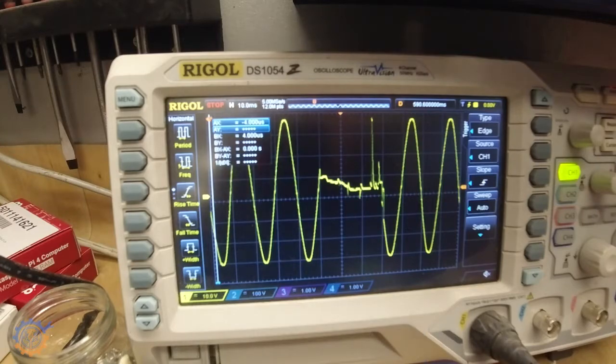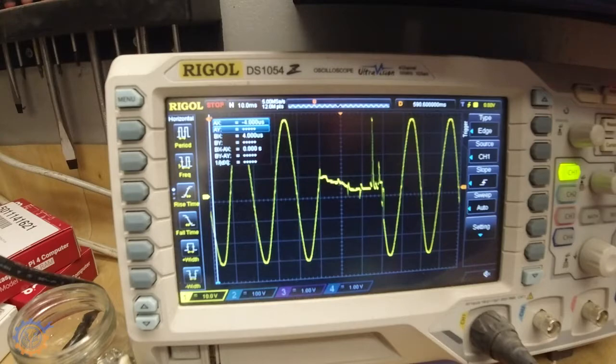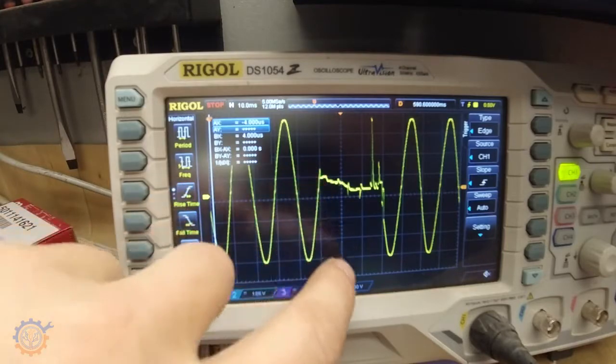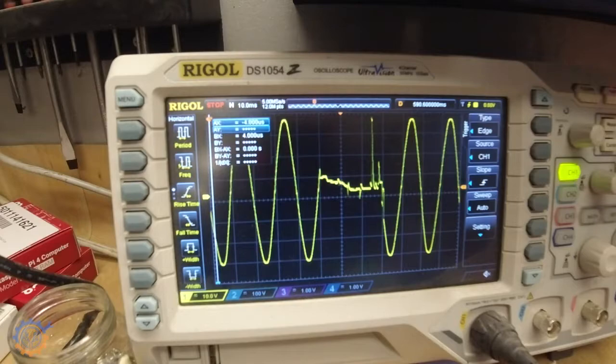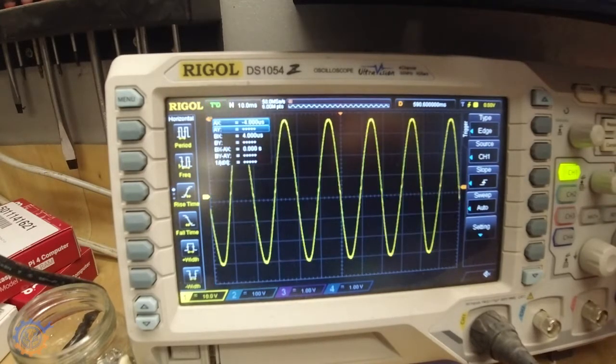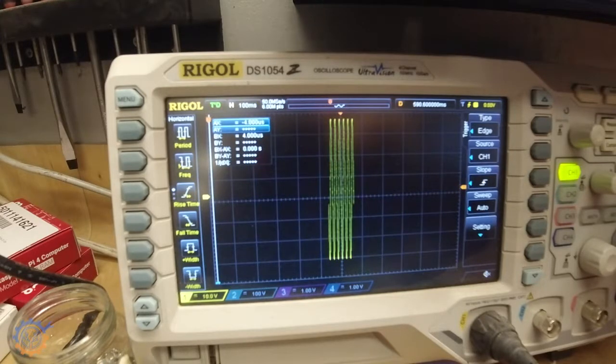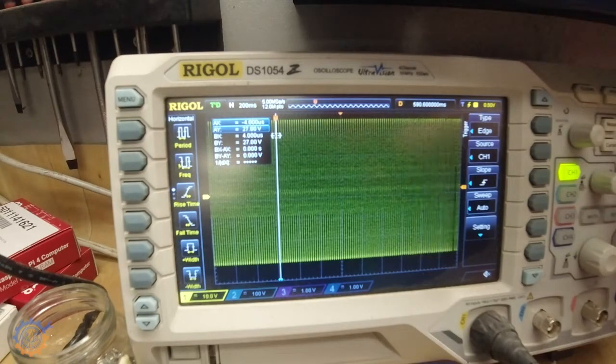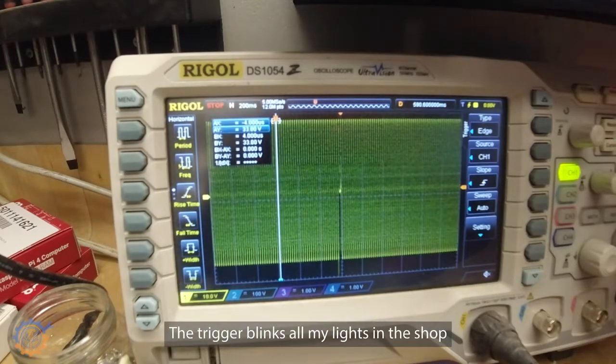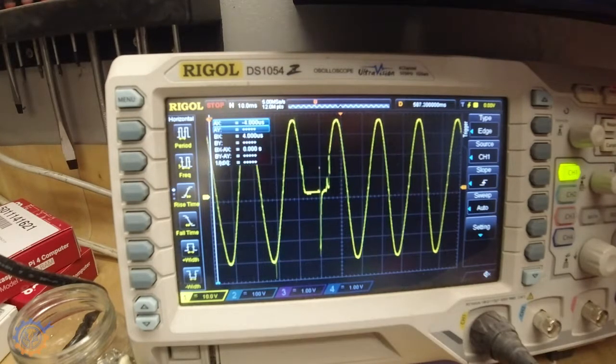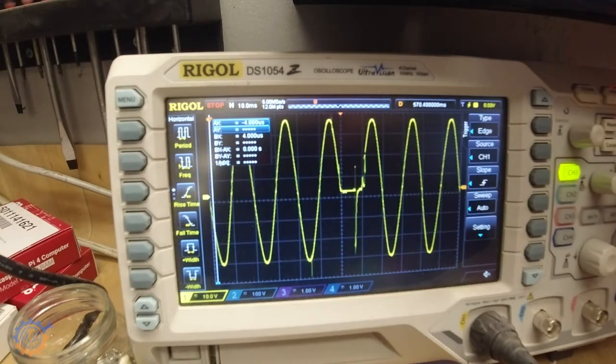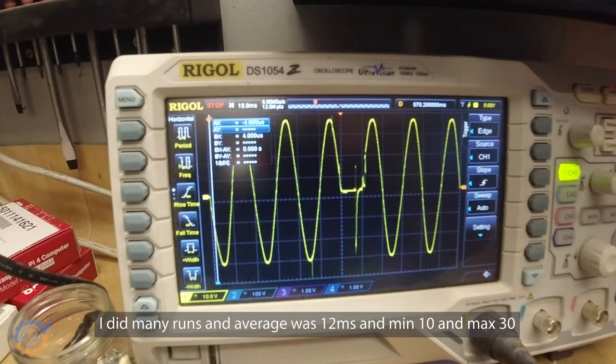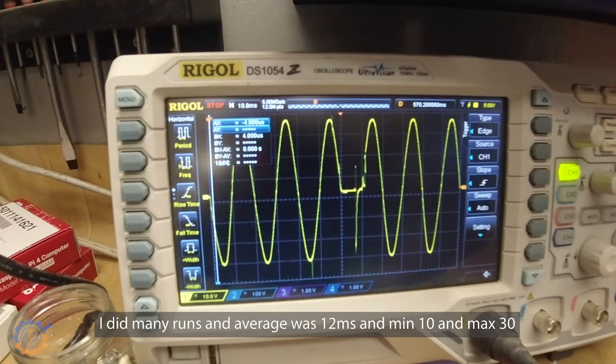The trigger time here depends very much on how it actually slaps from one side to another and when you do it. You can also clearly see that there is no zero point trigger of course. It is a contactor. It starts in the middle of the pulse. So let's do another test and see how it does the next time. Let's run it again. Zoom out a little bit. There we have another trigger. Let me zoom in. And in this case we had an outage of around 10 milliseconds.